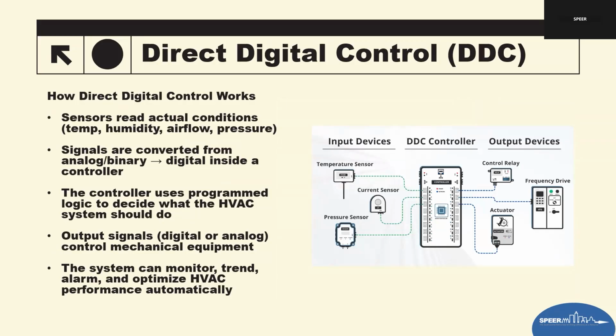DDC, direct digital controls. This is the backbone of modern HVAC system controls. Before we talk about advanced controls and default requirements in the 24, we must understand what the DDC system actually does and why it matters. So it basically works with sensors that read actual field conditions. Everything starts with real world measurements. Sensors capture temperature, humidity, airflow, pressure, whatever the system needs to make decisions.